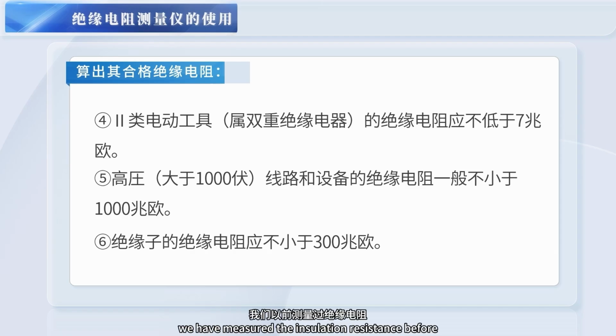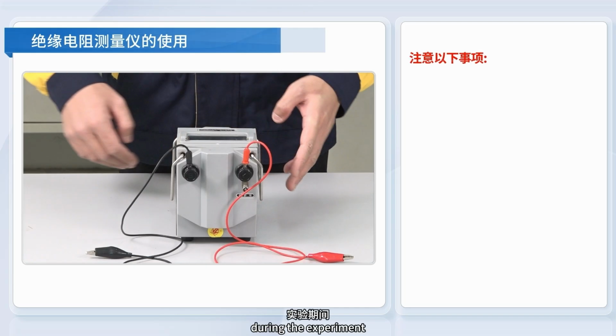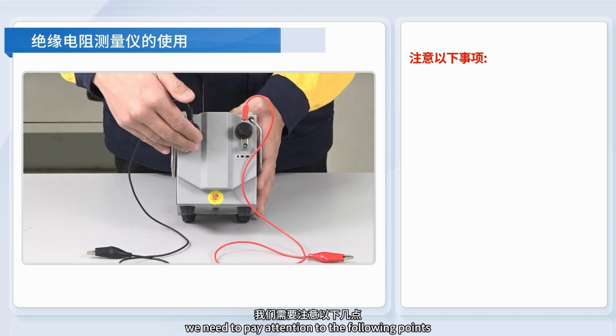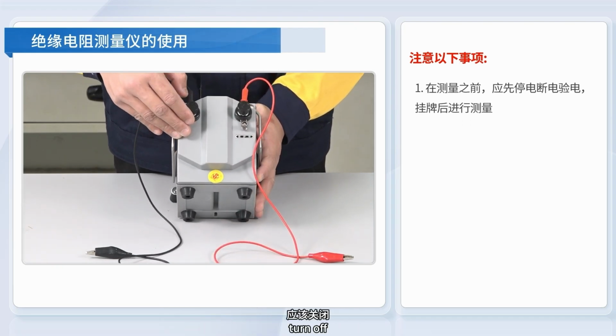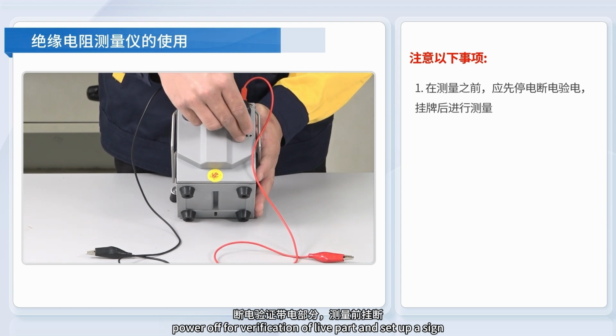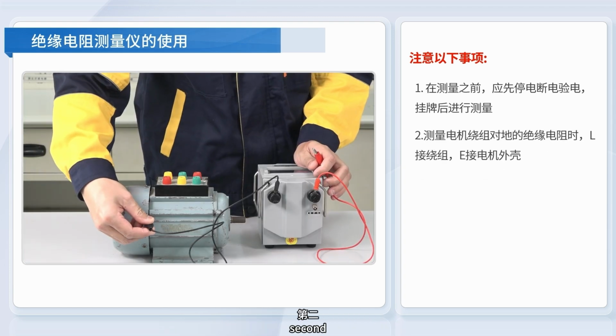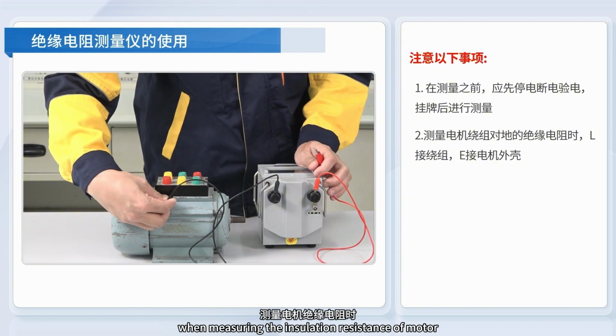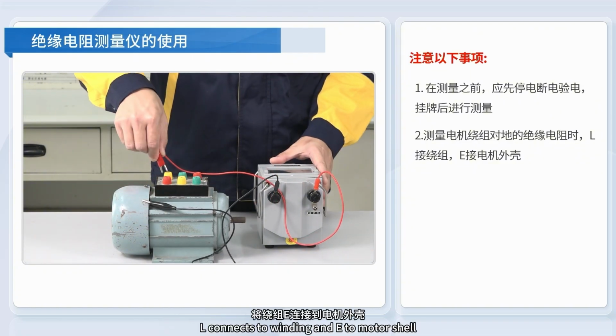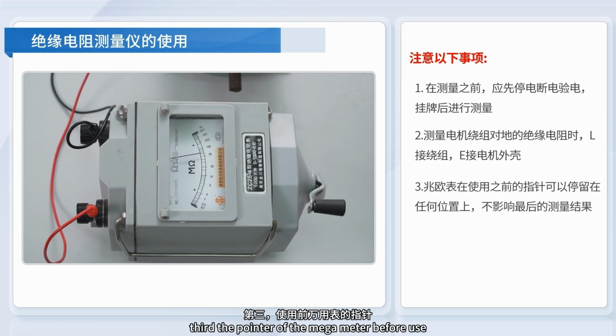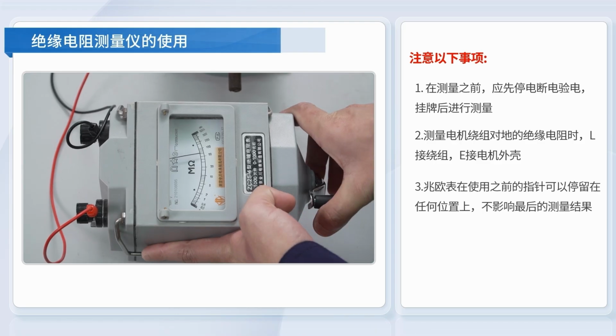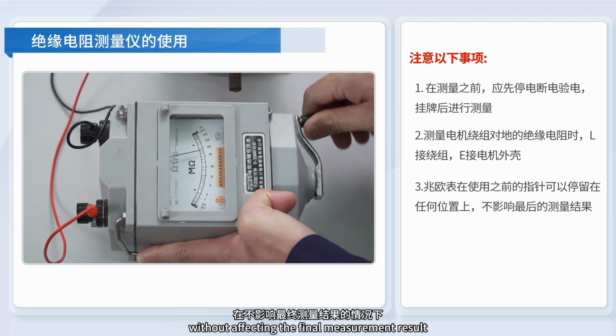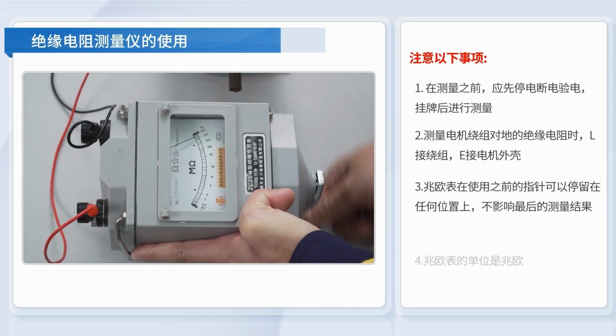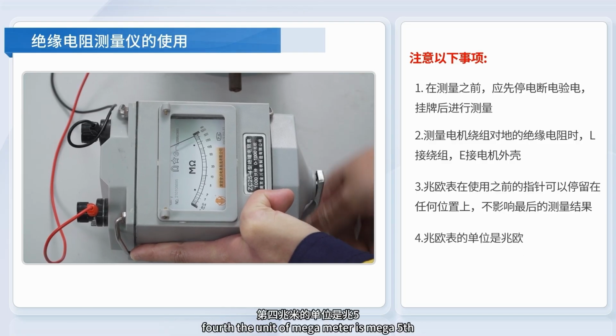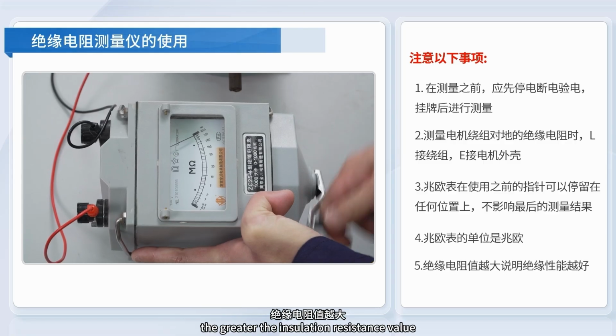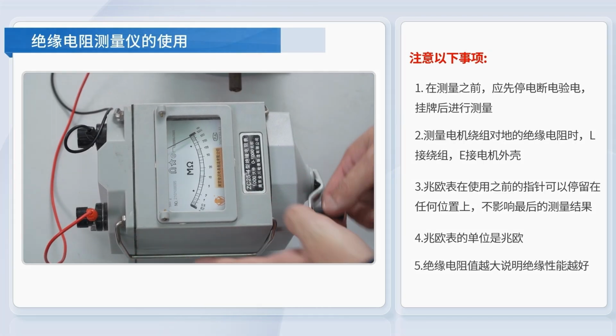We have measured the insulation resistance before. During the experiment, we need to pay attention to the following points. Firstly, before measurement, power off, verify there is no live part, and hang up a warning sign before measuring. Second, when measuring the insulation resistance of motor windings to ground, L connects to the winding and E to the motor shell. Third, the pointer of the megohmmeter before use can stop at any position without affecting the final measurement result. Fourth, the unit of the megohmmeter is megohm. The greater the insulation resistance value, the better the insulation performance is.